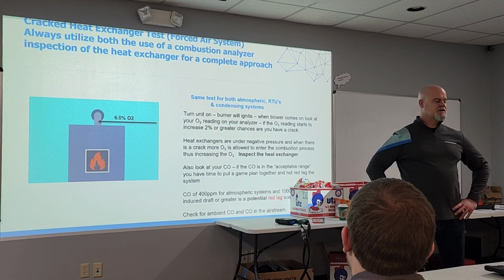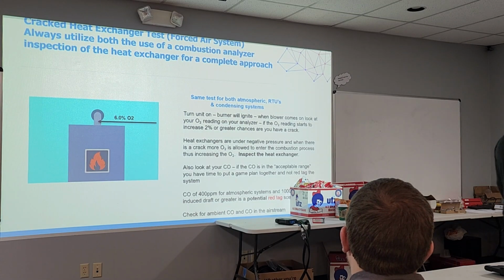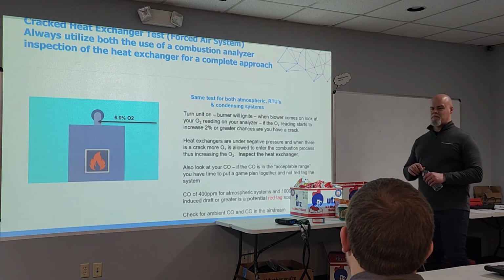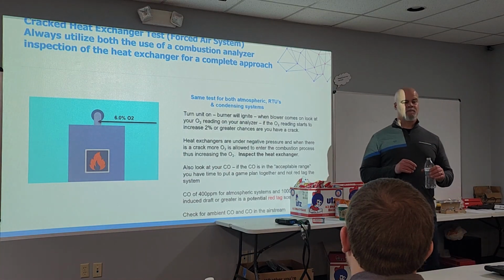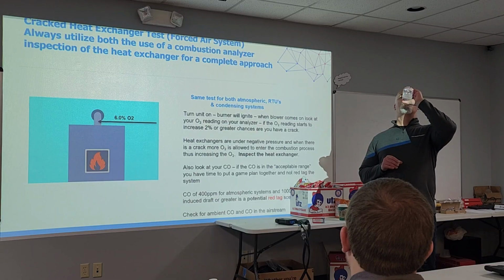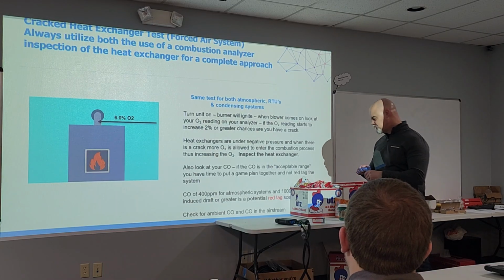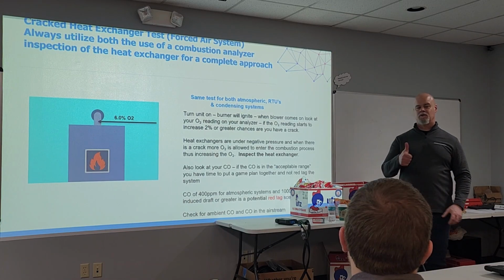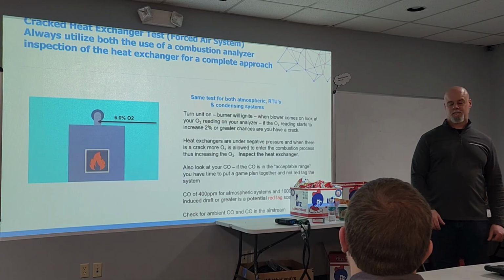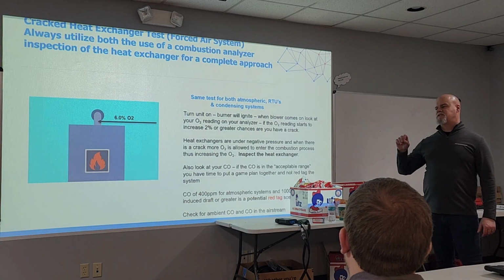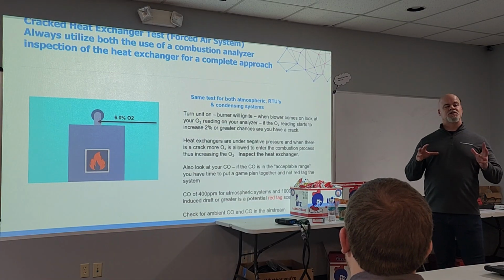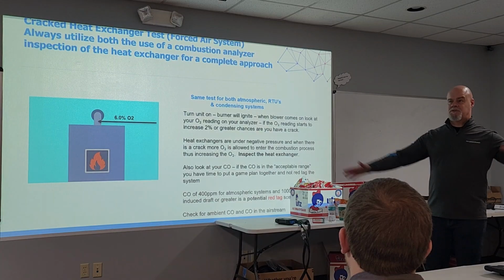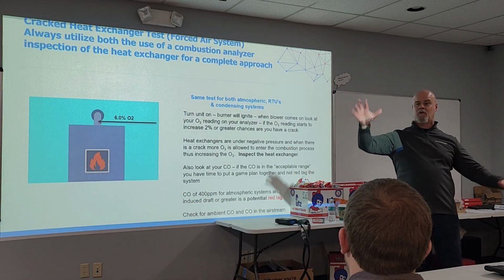You're going to notice your oxygen plummeting. Why? Because you're no longer measuring ambient air conditions, you're now measuring byproducts of combustion. You're going to notice your CO on the rise because it's the exact same thing. Within 15 to 20 seconds though, your oxygen is going to stabilize - it's bouncing, very irregular, and all of a sudden it's going to settle.